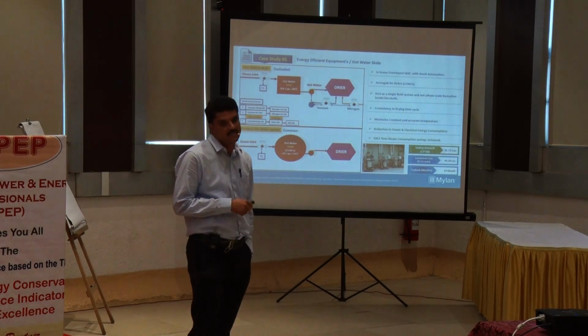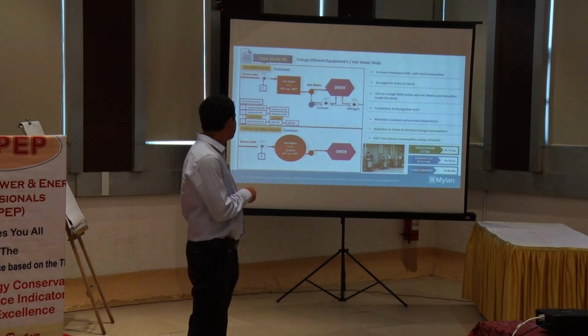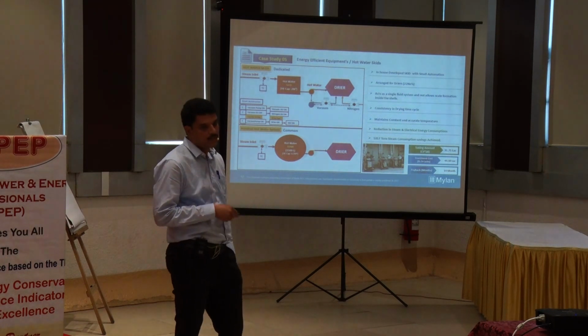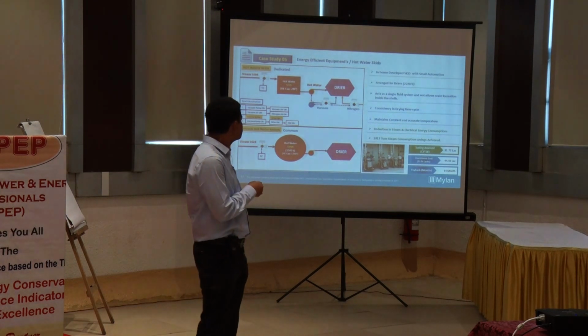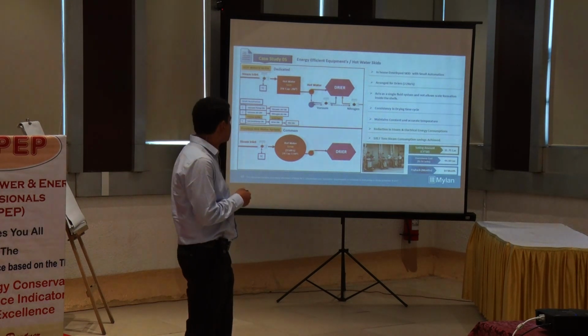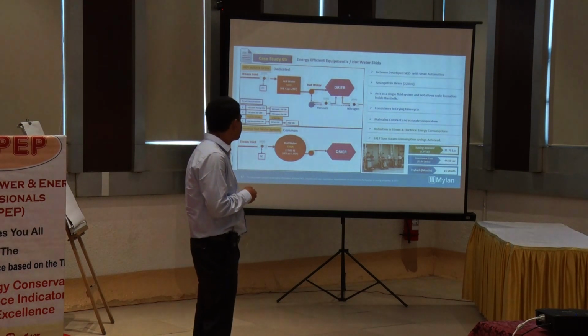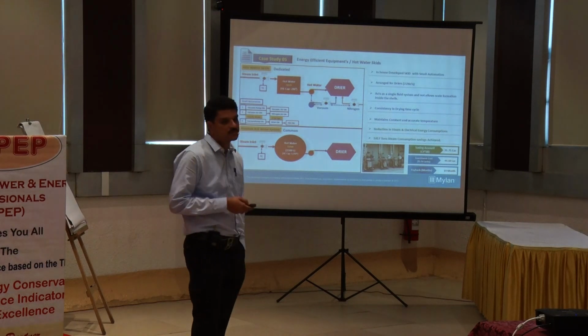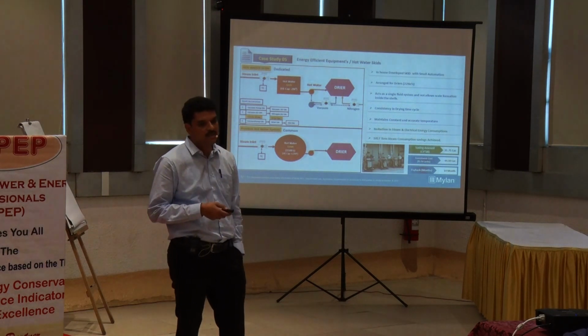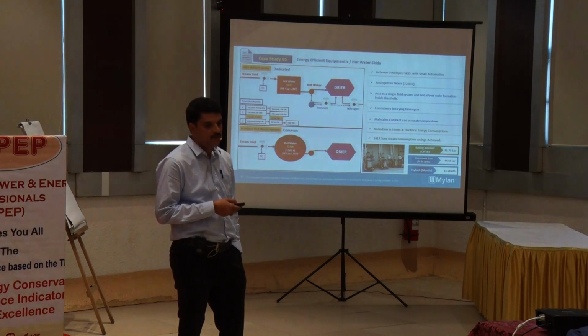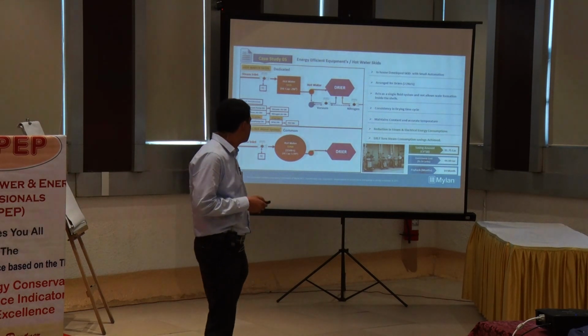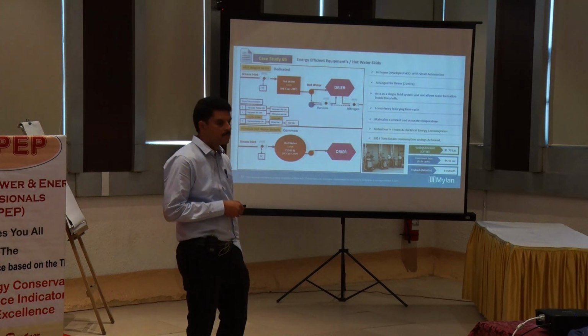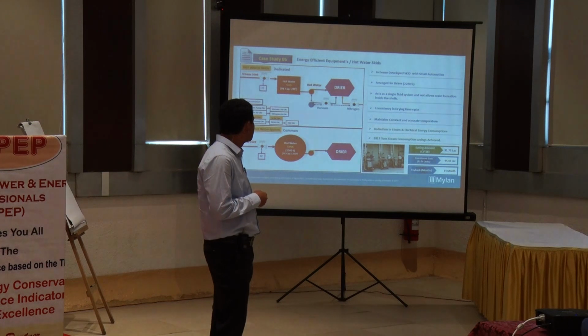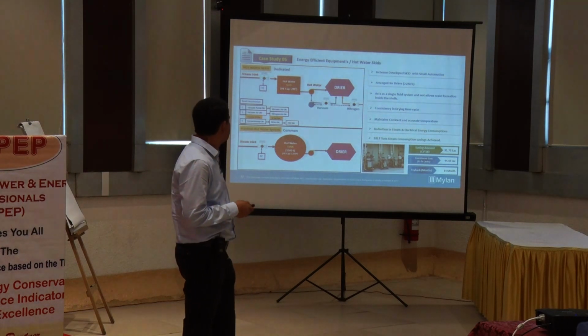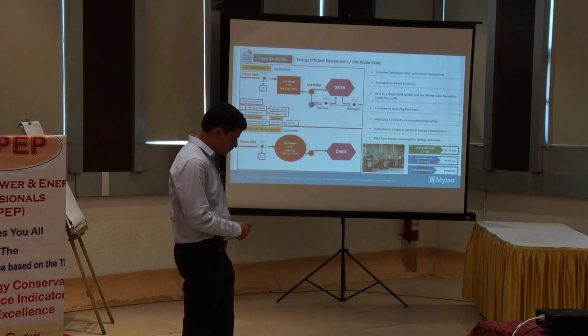So this is the conventional hot water systems. With the jacketed tanks, we have replaced with instant heating hot water skids. So these are developed in-house with small heat exchangers and with small automation. It's arranged for 22 dryers and acts as single feed system. It does not allow scaling. Actually, inside the tank we are using DM water, and it is indirect heating and cooling system through heat exchanger. With that, we are able to maintain the consistency in the process, and maintain reduction in the steam and electrical energy consumption. These are the savings. Investment 44 lakhs and payback is 14 months.